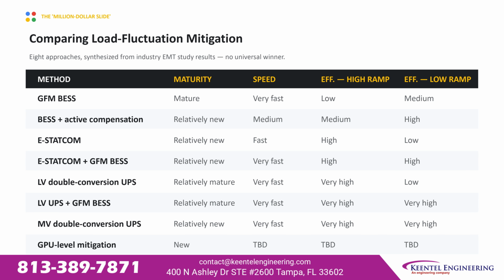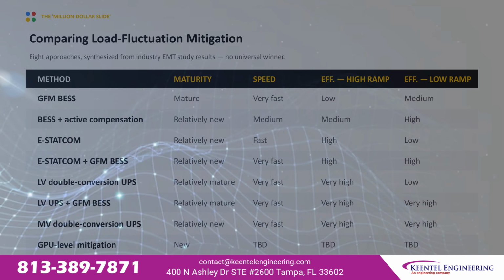Pair it with grid-forming battery storage, though, and you get very fast response with high efficiency across both. Low-voltage double conversion UPS is very fast and very efficient at high ramp rates, but weaker at low ramp rates, unless paired with grid-forming battery storage, which makes it very efficient across both. Medium-voltage double conversion UPS, while relatively new, is very fast and very efficient across both. And GPU-level mitigation is emerging, but its maturity, speed, and efficiency are all still to be determined.